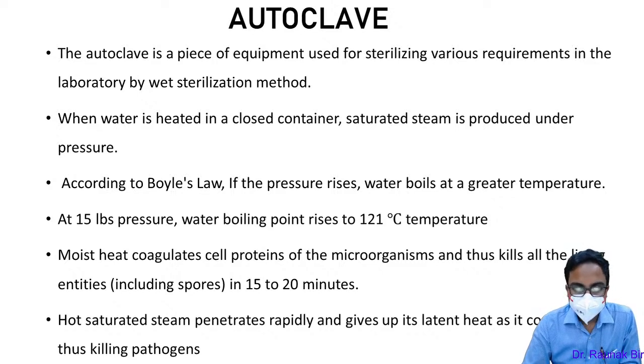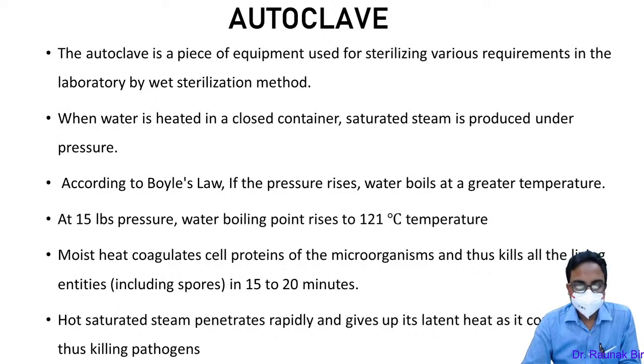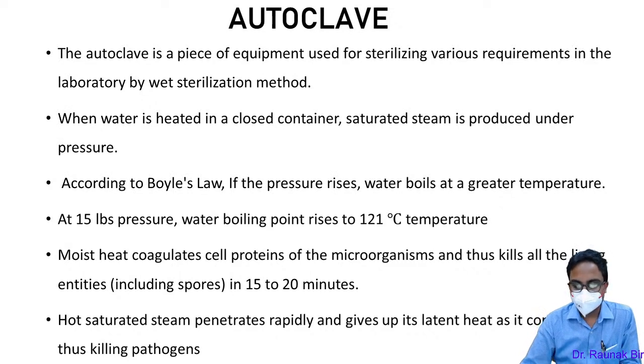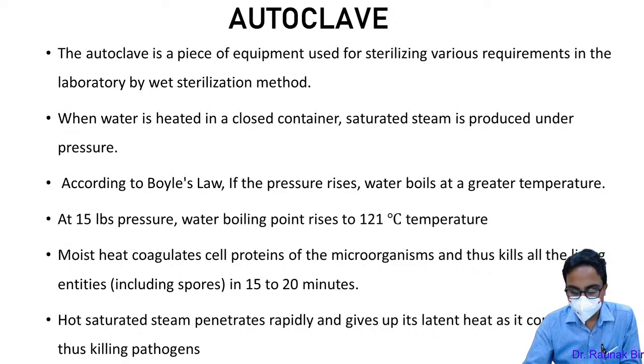At 121°C, if we keep the articles for 15 to 20 minutes, due to moist heat coagulation of protein, most organisms including spores are destroyed, causing sterilization of the articles. Hot saturated steam penetrates rapidly and gives up its latent heat; due to the transfer of this latent heat, the pathogen's proteins and other structures are coagulated, ultimately causing destruction of the pathogen.